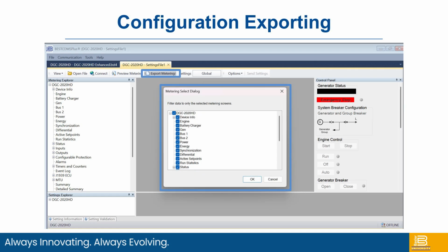Configuration exporting. As I said, with the BESTCOMSPlus software tool, you can work offline. You can build your configuration file and then download it into the DGC. What's nice is if you're coming up to a unit that you've not programmed, you can connect, and as long as you have access, you can download that program from the DGC, so you can utilize it for another application, or take it back to the office or truck, change settings, and then go back and download it and program the DGC.